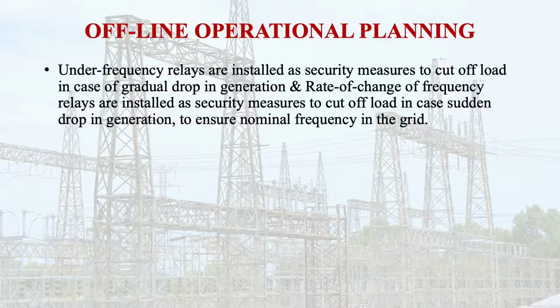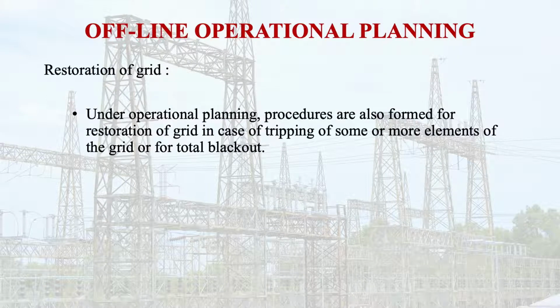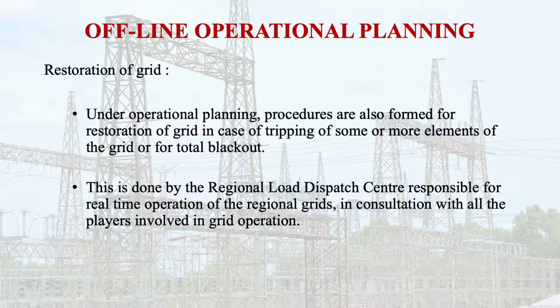So under frequency and rate of change of frequency relays are installed as security measures to cut off load in case of a gradual or a sudden drop in the generation, especially to ensure nominal frequency in the grid. Under operational planning, procedures are also formed for restoration of the grid in case of the tripping of some or more elements of the grid or for total blackout. So this is done by the regional load dispatch centers responsible for the real-time operation of the regional grid.